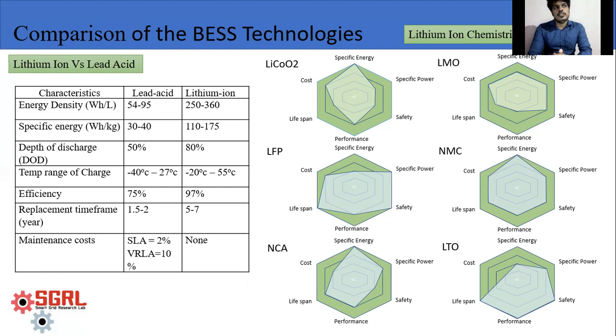The other term is SOH, state of health level, which depends on the life cycle of the battery. If initially we have 2000 life cycles, and we discharge the battery several times, say to 50% SOC level repeatedly, until the life cycle becomes 1000, then the SOH level will be 50%. It depends on the health and life cycle of the battery, its efficiency, replacement time frame, and maintenance cost.